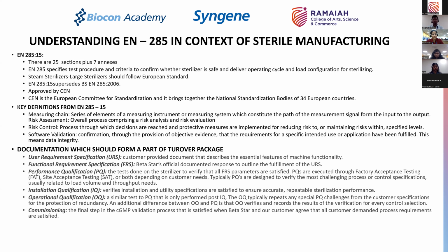All these are installed, and you check that yes, it is okay, the equipment is level, it is not sitting at an angle, so that the slope is incorrect. All those checks are done in what is called an installation qualification.